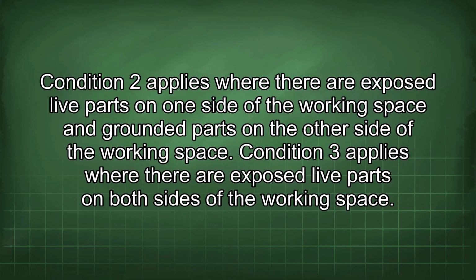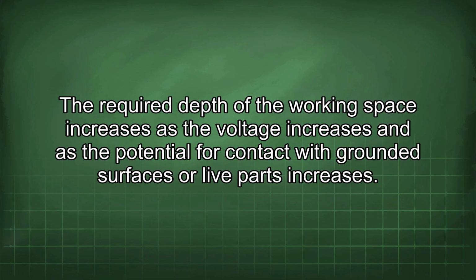Condition 3 applies where there are exposed live parts on both sides of the working space. The required depth of the working space increases as the voltage increases and as the potential for contact with grounded surfaces or live parts increases.